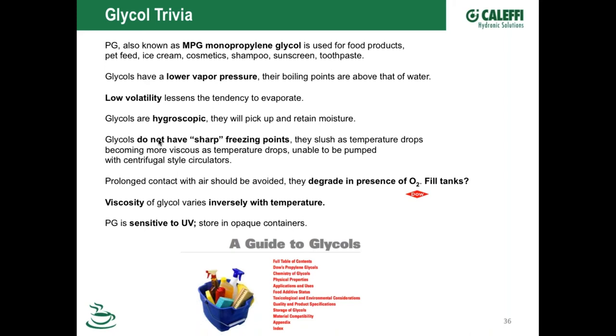My bottom line: when you mix a percentage of glycol, don't mix a real strong percentage like 50 or 60% glycol in water - you don't need that low of a freeze protection rate. What you're really concerned about is the burst temperature of the fluid, not so much the point where it turns to slush and is hard to pump. You just don't want to burst pumps. People sometimes think that for a snow melt job they need a strong glycol solution because it could get below zero, but you might just lose your ability to pump it on a 30-below day - it's not going to burst your pipe. So pay attention to the blend ratios.